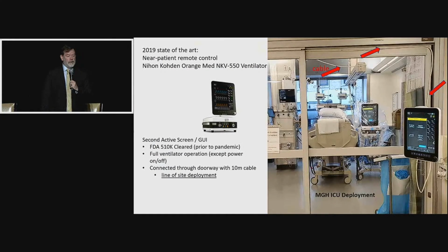And interestingly enough, Nihon Kohden OrangeMed, prior to the pandemic, had already obtained a 510(k) for a remotely controllable ventilator, which has a second screen, a second GUI, and a 10-meter cable. So you can see in the photo the white cable that's running from the second screen outside the room to the ventilator inside the room. So the FDA was willing to clear what was considered a lower risk application. Instead of connecting over a network to a ventilator that was far away, you're performing near-patient remote control with a dedicated cable connection. So that also required line of sight. So you could look through the window, right?